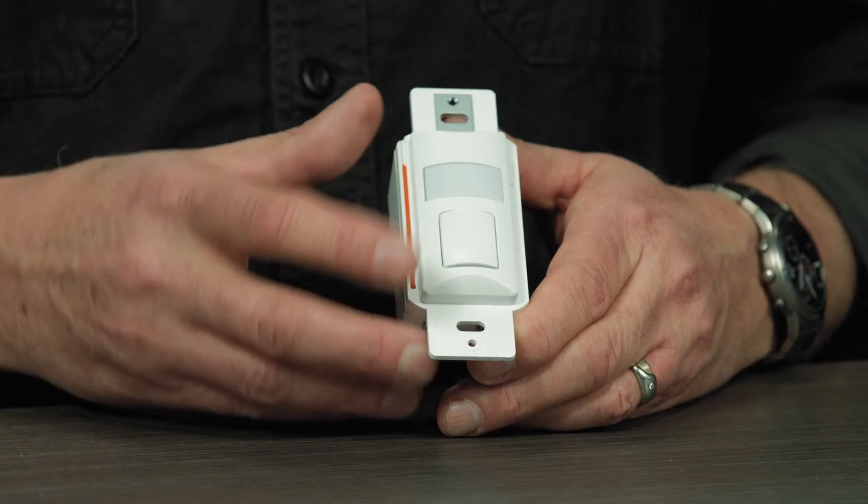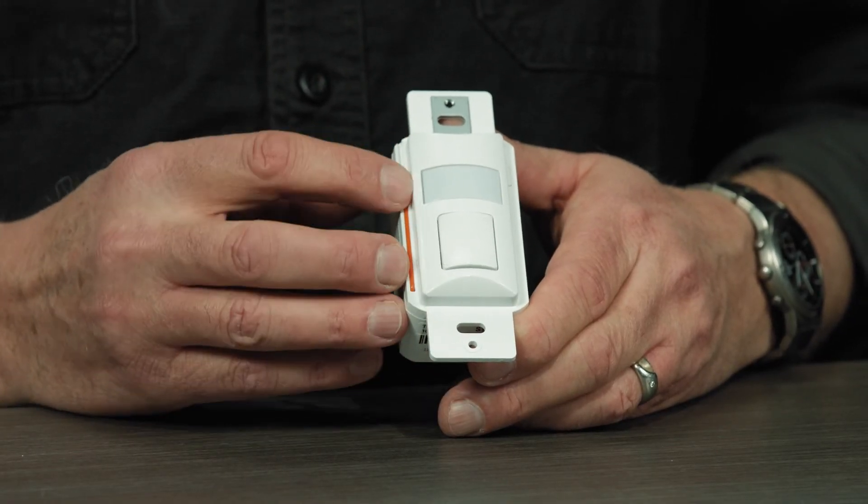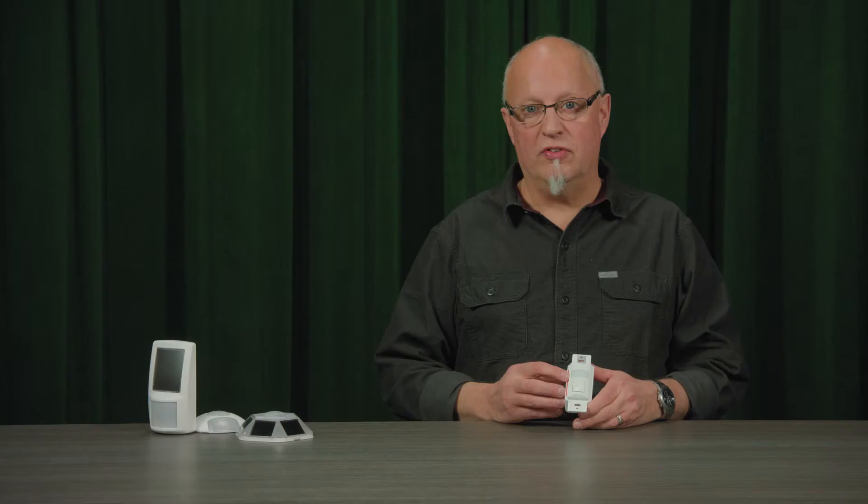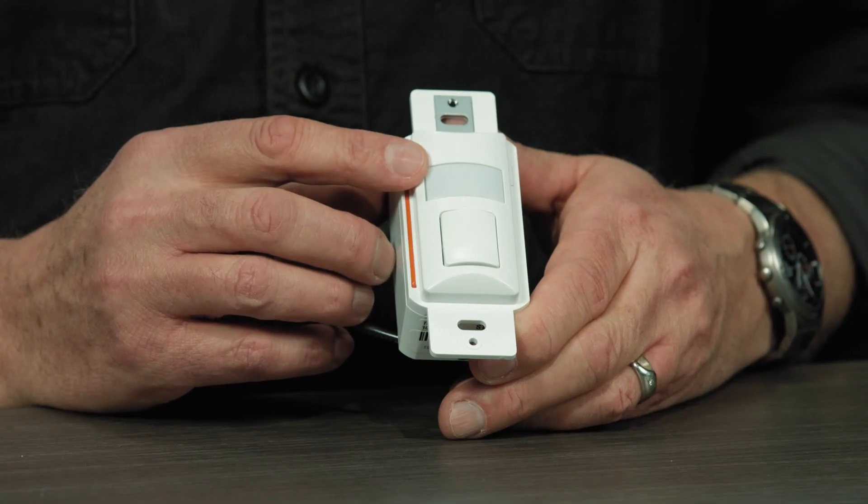This allows us to use this sensor station for Title 24 applications where you have controlled receptacles and you want to control those receptacles with an occupancy application but you're using the sensor for a vacancy application for your lights. This allows you manual on, auto off with the vacancy for your lights and auto on and auto off for your controlled receptacles.